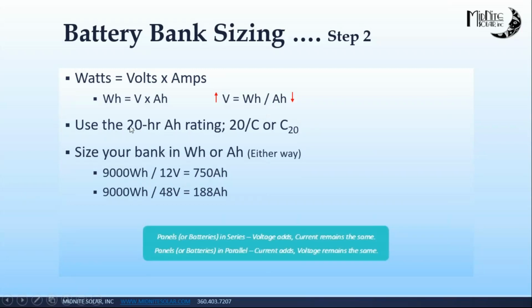So something to consider. When you size your batteries, you always want to reference the 20-hour amp-hour rating. Oftentimes it's printed on the top of the battery. What you really need to do, when you've identified your batteries, is get a specification sheet from the manufacturer, and it's going to have a lot of information on their charging voltages, amp-hour capacity, temperature compensation issues, max charging current, a whole bunch of stuff that you need to program into the charge controller and your inverter charger. But use the 20-hour rating. You'll see that they have 1 hour, 5 hour, 10 hour, 20 hour, 100 hour ratings. But the 20-hour rating is most closely associated with a 24-hour solar day.